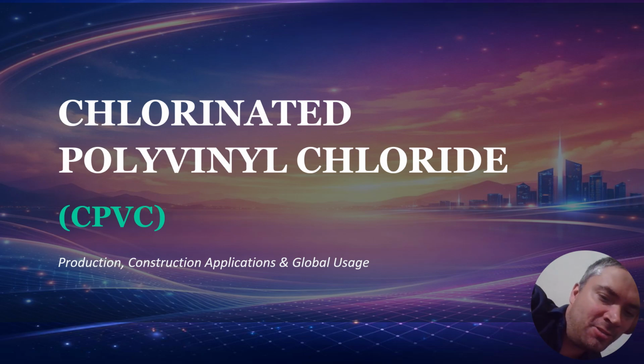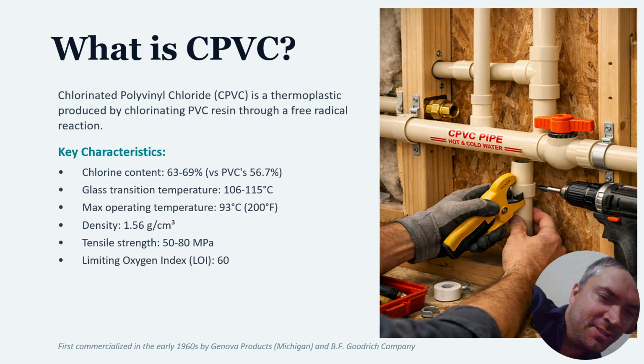Chlorinated polyvinyl chloride, CPVC. What is CPVC? Chlorinated polyvinyl chloride is a thermoplastic produced by chlorinating PVC resin through a free radical reaction. The key characteristics: chlorine content is 63 to 69%. The glass transition temperature is about 106 to 115 degrees Celsius. The max operating temperature is 93 degrees Celsius. Limited oxygen index is 60.